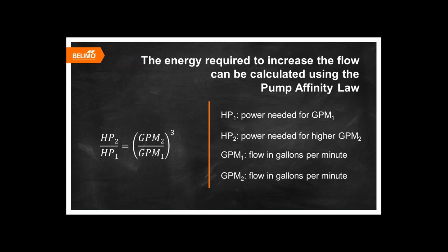Let's go back to the classroom and see how that additional energy increase works for our pumping energy. This is a formula called the Pump Affinity Law. We use these differences in flows to determine the amount of extra pumping horsepower that's necessary to provide the additional flow. Let's take the variables from our example and enter them into the equation.